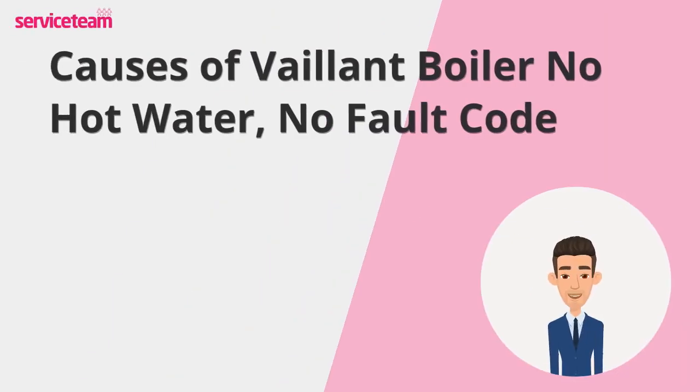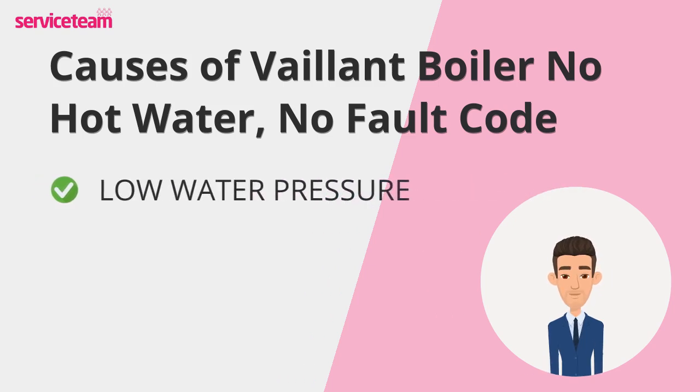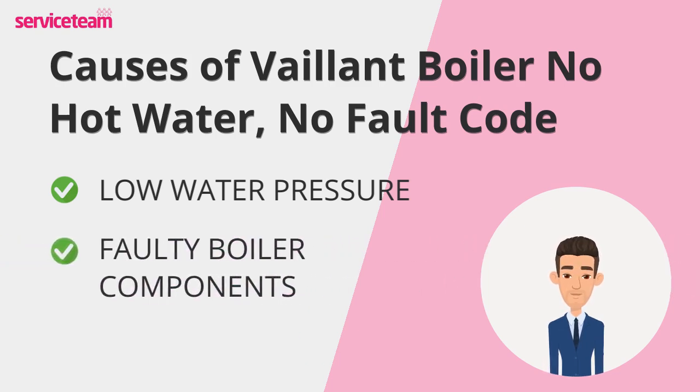Let's go through the most common reasons for the Vaillant Boiler No Hot Water, No Fault Code. First up, low water pressure — it's likely a sign of insufficient water pressure, which can disrupt water flow and prevent proper heating. Next, faulty components could be to blame. For instance, the F27 code points to a flame detection issue, while problems with parts like thermistors, pumps, or diverter valves may also cause your hot water to stop flowing.